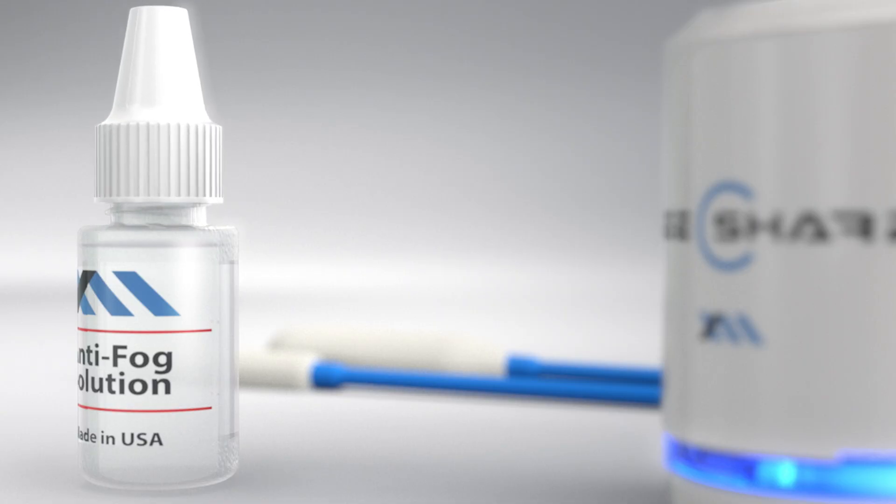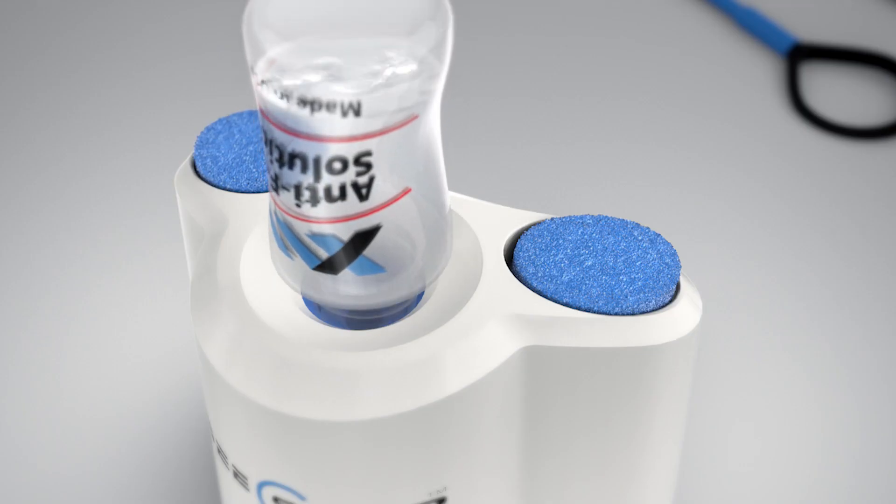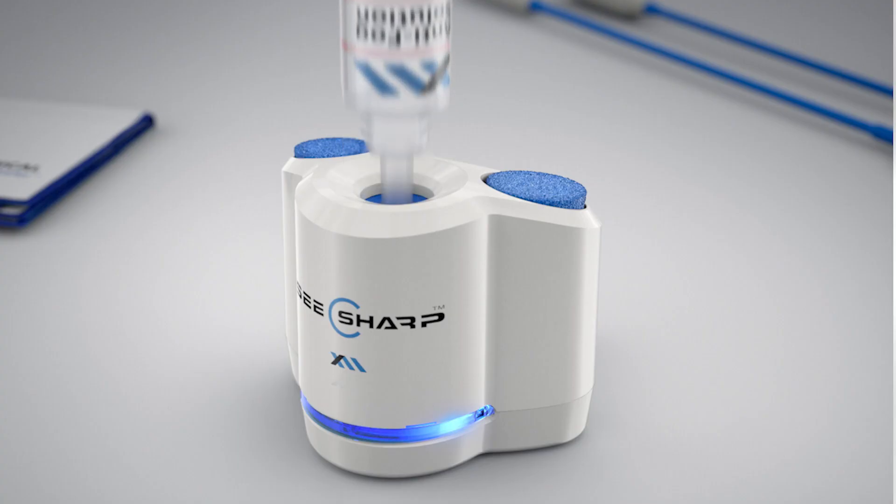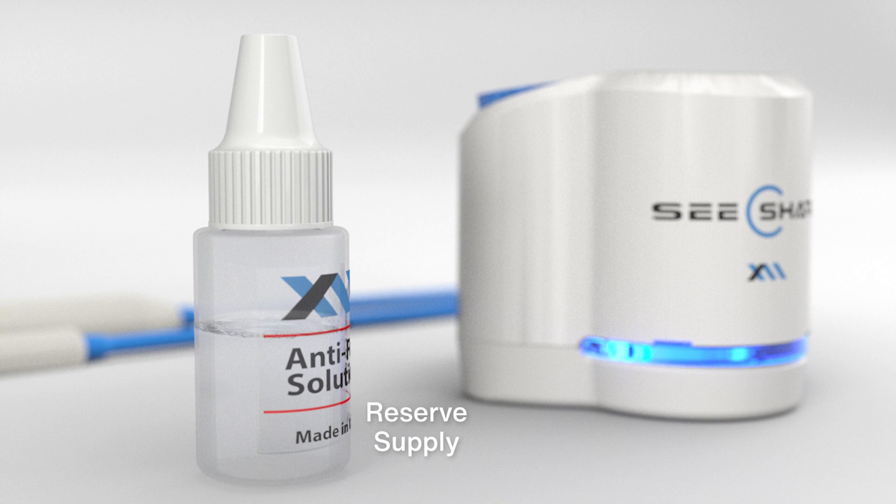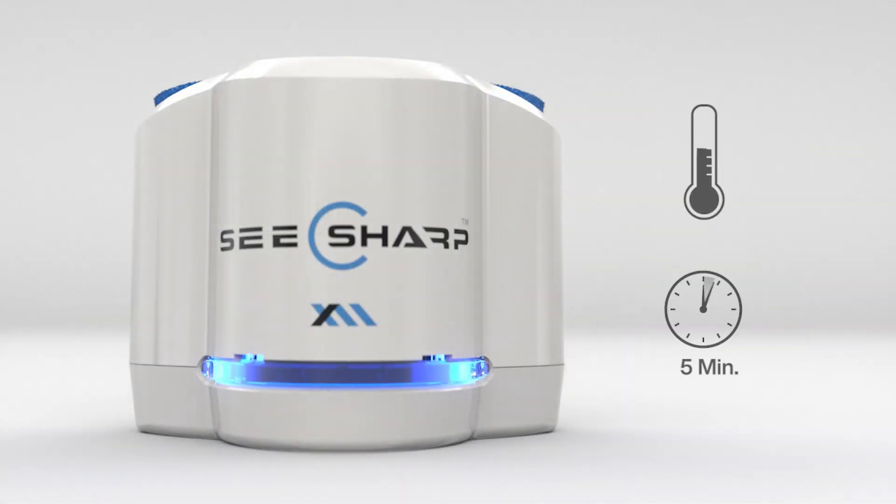Remove the lid from the anti-fog bottle and completely insert the open nib into the See Sharp reservoir. Squeeze the sides of the anti-fog bottle, dispensing approximately one-third of the solution into the See Sharp reservoir, as indicated by the red lines on the bottle's label. Return the lid to the bottle and store the excess solution for potential later use. Allow five minutes for the See Sharp unit to reach optimal temperature.